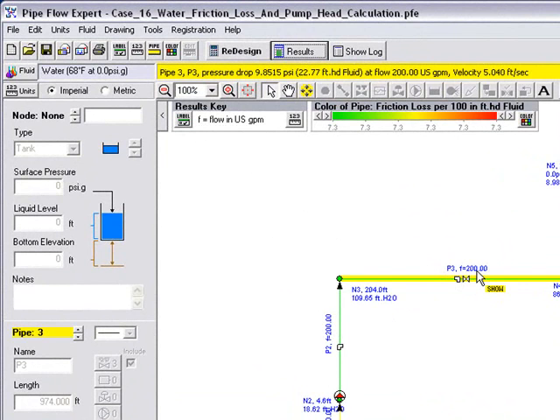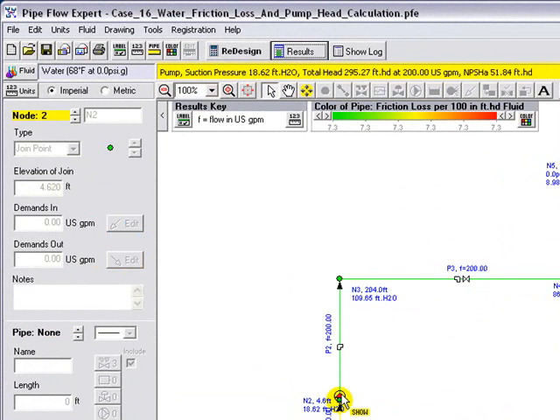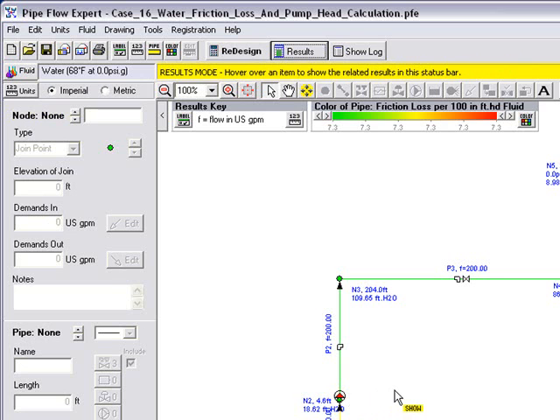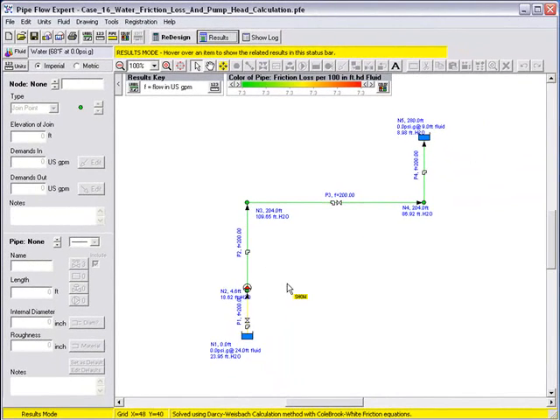We can also hover over the pump. We can see in the yellow status bar window at the top of the screen, the suction pressure of the pump is 18.62 feet. The total head added by the pump is 295.27 feet, produces a flow of 200 US GPM, and the NPSH available is 51.84 feet head of liquid. So we've solved this system and we've solved the pump head required to move the liquid from the base tank to the top tank to overcome all the friction losses and elevation changes in the system.